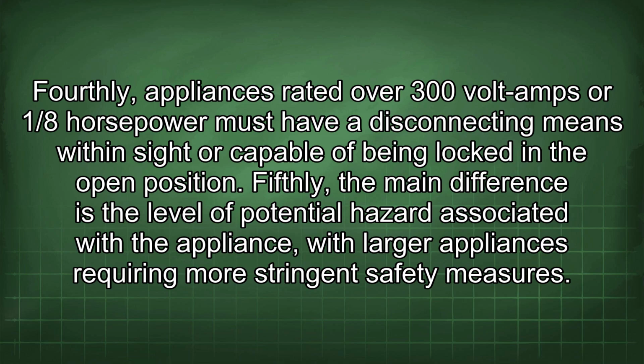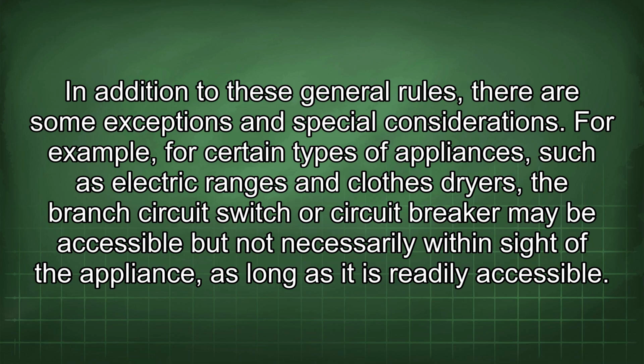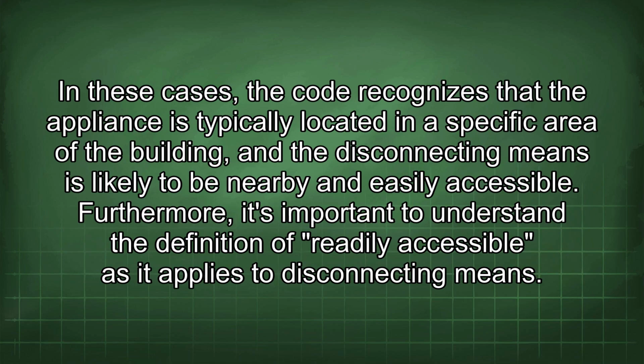In addition to these general rules, there are some exceptions and special considerations. For example, for certain types of appliances, such as electric ranges and clothes dryers, the branch circuit switch or circuit breaker may be accessible but not necessarily within sight of the appliance, as long as it is readily accessible. In these cases, the code recognizes that the appliance is typically located in a specific area of the building, and the disconnecting means is likely to be nearby and easily accessible.